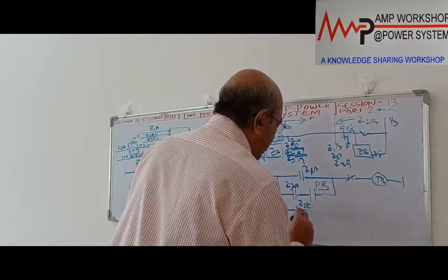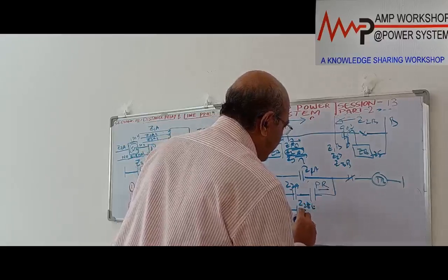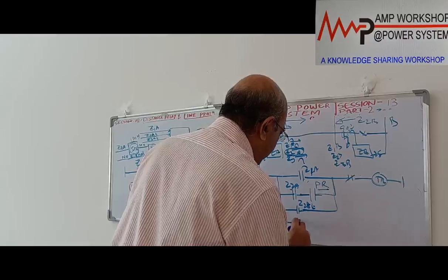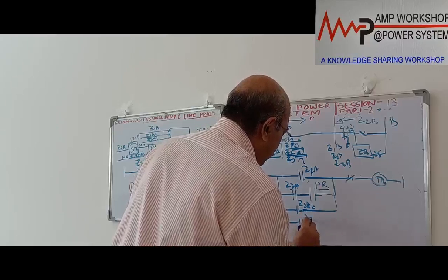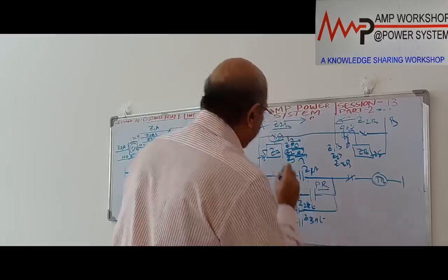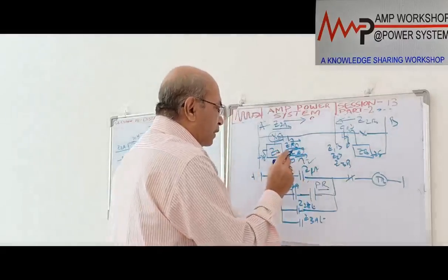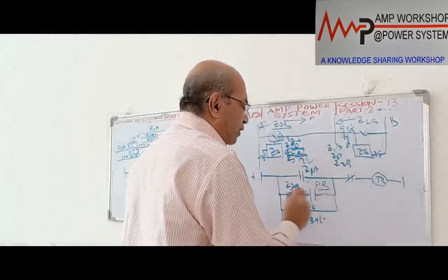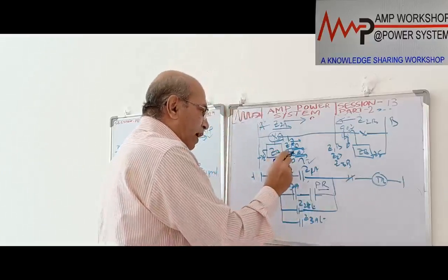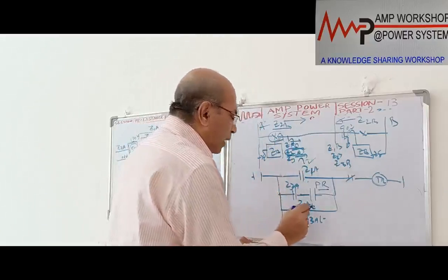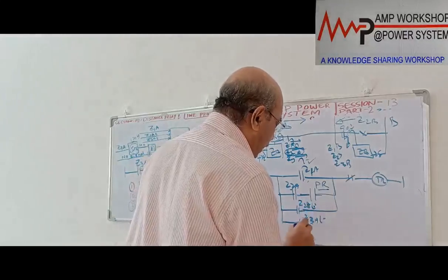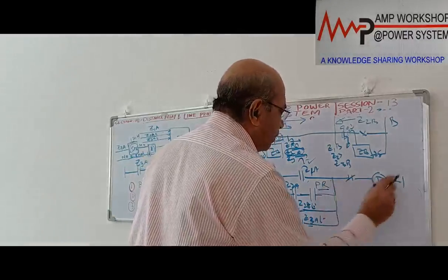Now third, we said what is that? Z2AT, this is also giving a tripping component. Then Z3AT, here are three elements. The first element is instantaneous trip, the second element with the permissive is tripping instantly. But if the second unit permissive does not come, then it will take the normal time delay of 250 milliseconds, it will be 450 milliseconds, then it will give the tripping command.